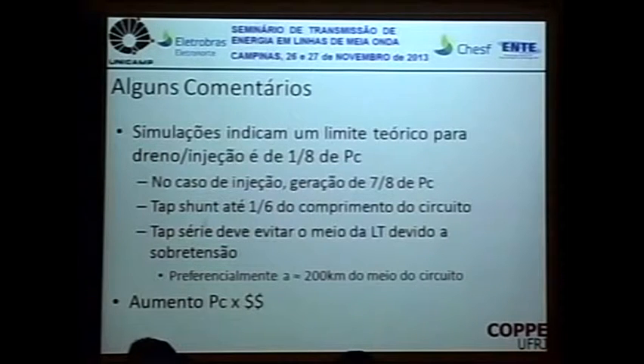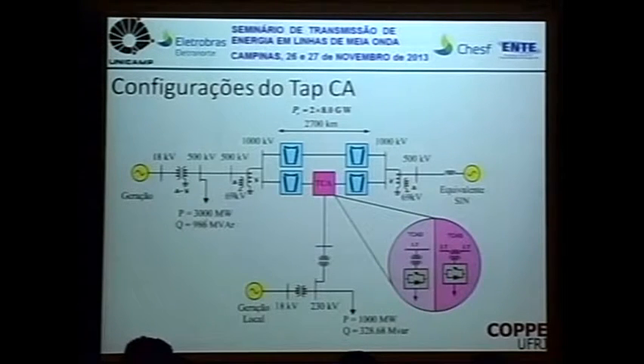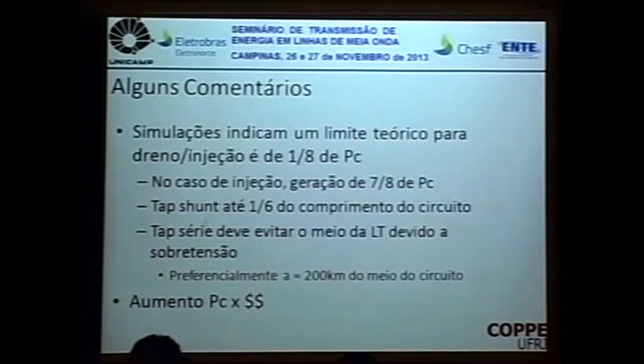Series tap, although it is ideal for the middle of the line, we have to remember, since we are working with two lines, in case of loss of one of them, the whole transport will happen through the other. This would cause an increase in voltage that would theoretically go to 2. But since we worked in this system representing the corona effect, we can see that the corona effect drains a lot of this overvoltage, getting it up to 1.7, 1.6, depending on the characteristics of the circuit. With that, we would have to stay basically up to 200 kilometers from the middle to avoid this middle point, which is a point where your line needs to be over-isolated in case you're working with two circuits.